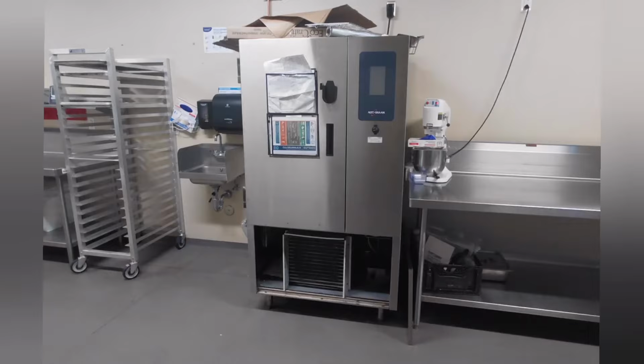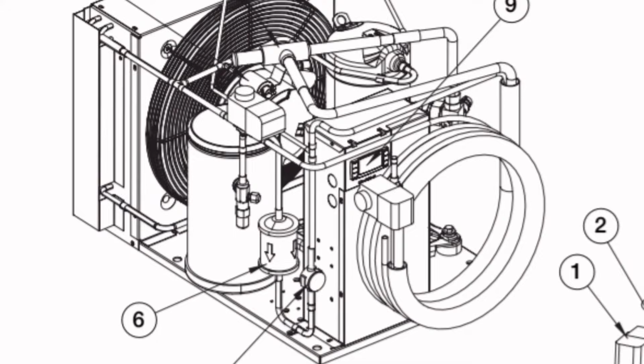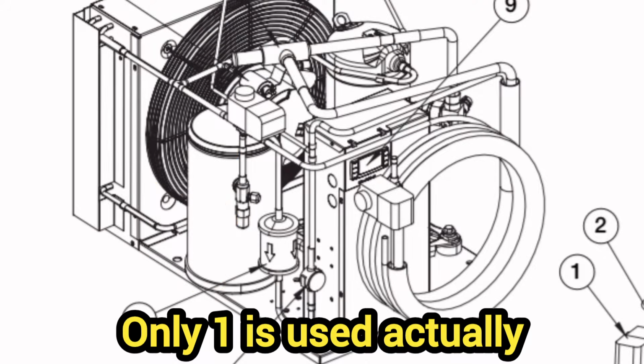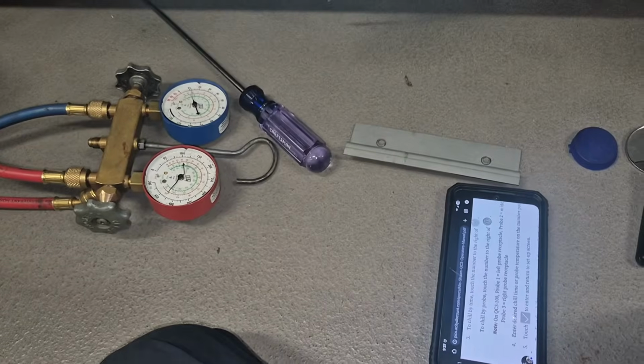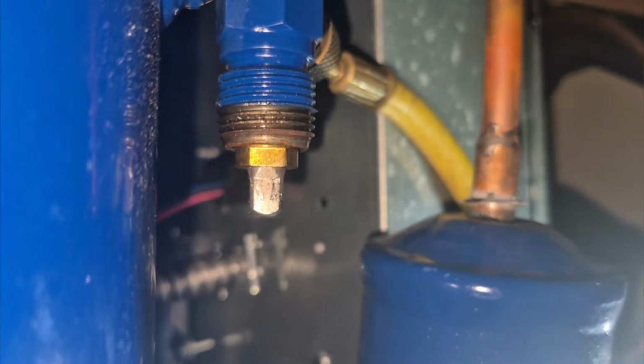Now the way this unit works is it will satisfy the demand and pump down using these solenoid valves, but this one can't do it. This is a for sure way to pump it down. You close the receiver service valve. Now you should be able to always do this, and if you ever run into problems doing this, it means that something else is wrong.